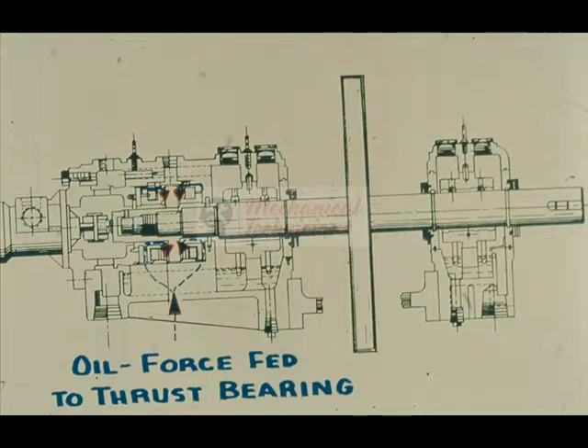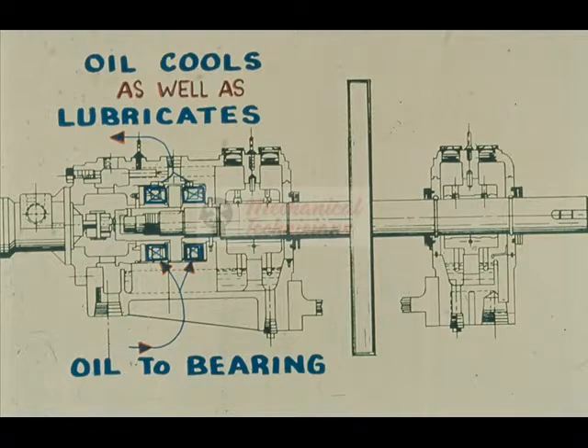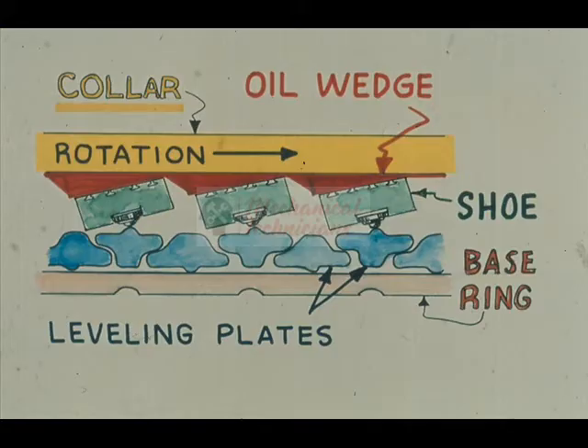Lubricating oil as specified by the manufacturer is force-fed into the thrust bearing housing and is directed through passageways behind the thrust bearing base ring and inward along the shaft to the thrust collar. A portion of the oil flows through the base ring, lubricating and cooling these components. A very important part of the oil supply, caused by the relative motion of the collar and the bearing shoes, is wedged in between the bearing shoes and the rotating collar. Hence, in operation there is no metal-to-metal contact of the shoe to the collar.